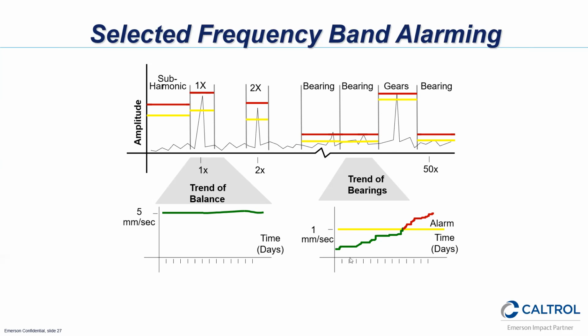Another trend plot. Here's an example of a trend plot where the low frequency amplitude is trending steady. So even if you had a device that didn't have peak view or wasn't monitoring the bearings on a separate band, the overall amplitude never increases much, but the bearing frequency and the faults going on are increasing into alarm. But these levels are so low, it doesn't affect the overall, and you'll never see it unless you're doing in-depth analysis.